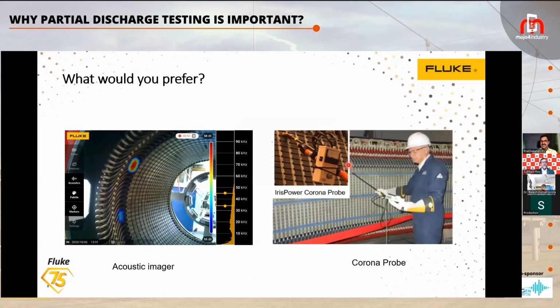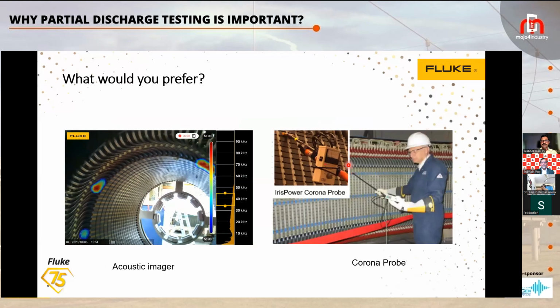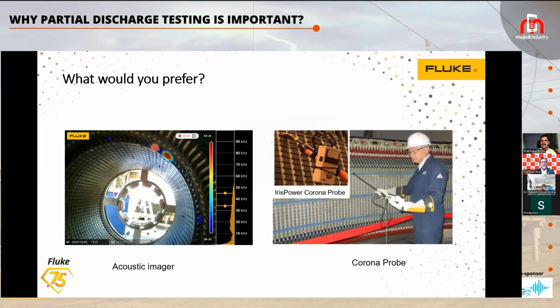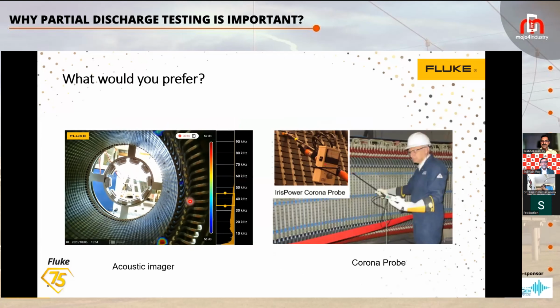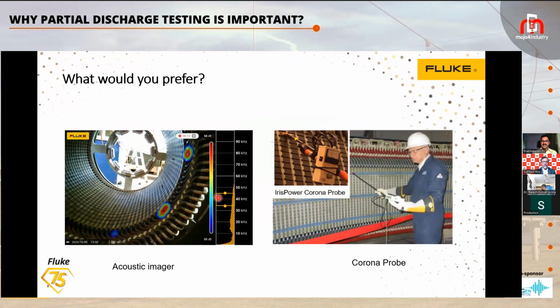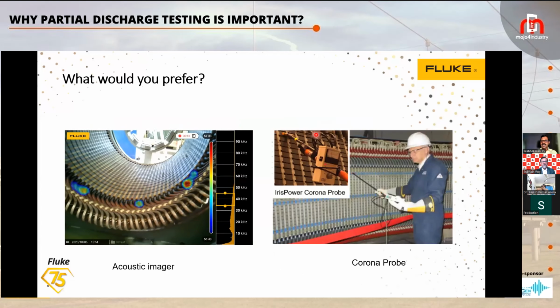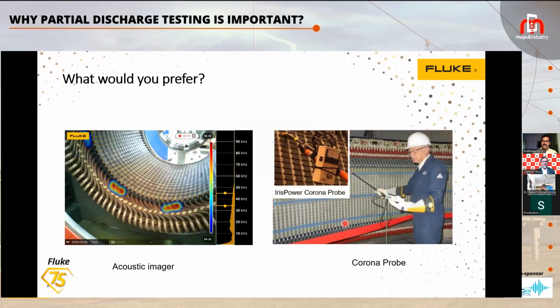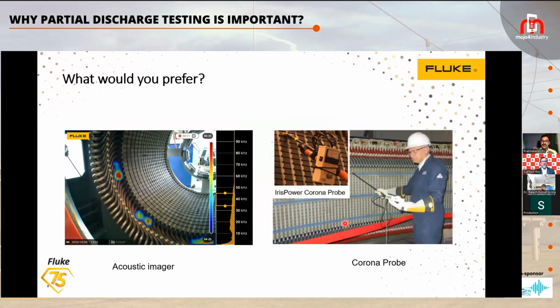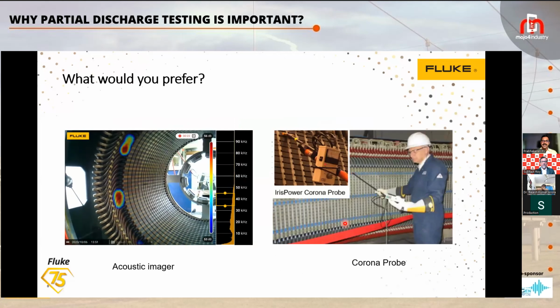This screen is showing you how an acoustic imager can help you with partial discharge detection. This is actually the Fluke partial discharge detector screen. In earlier days, you had to use some kind of probe and expose yourself to the high voltage area. With a non-contact acoustic imager, you can stay far away from the high voltage areas and still get the complete picture of the acoustic or partial discharge signal. That is the advantage you get.